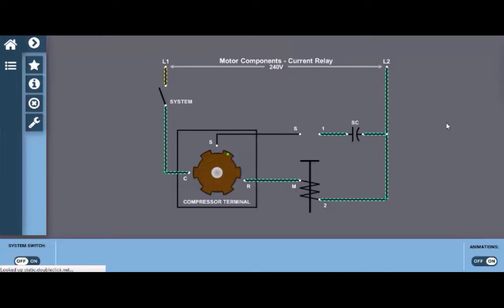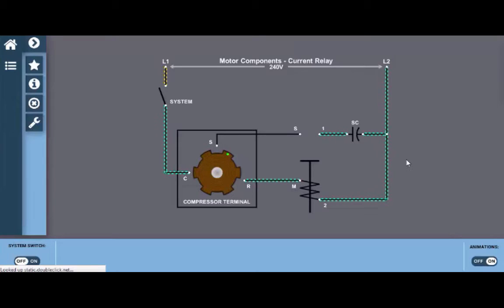The current relay allows the start capacitor and start winding to be engaged to turn the motor at startup.